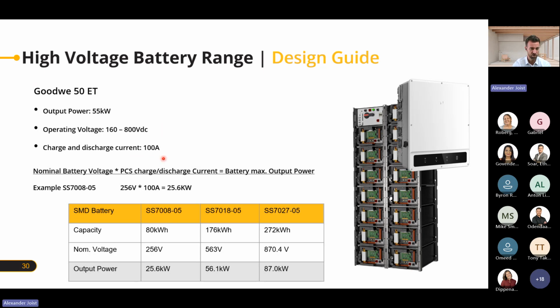And we have 100 amps charge and discharge current. So now we calculate, taking the example of the SS7008 with 256 volt, 256 multiplied by 100 amps is 25 kilowatt. So we can see that the output power with this inverter of the 80 kilowatt hour battery is only 25 kilowatt. Of the 176 kilowatt hour battery, it is only 56 kilowatt. So generally, if you want to have the full output power of this GoodWe 50 kilowatt inverter, you need to install 176 kilowatt hours of batteries, which sounds quite a lot.